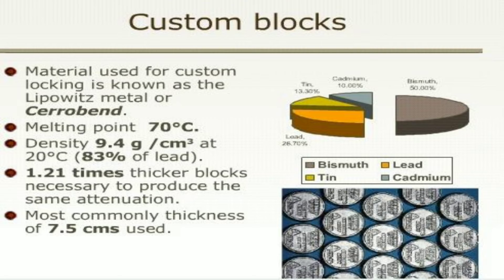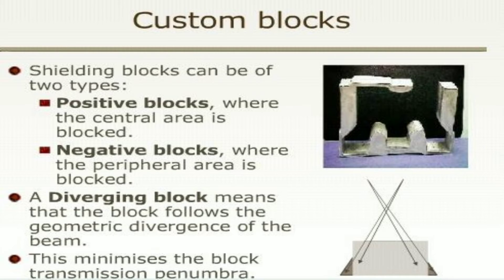Custom blocks are made up of Lipowitz/Cerrobend material which has a melting point of 70 degrees Celsius with a density of 9.4 grams per centimeter cube at 20 degrees Celsius, which is 83% of lead. 1.21 times thicker blocks are necessary to produce the same attenuation done by lead blocks, and the most commonly used thickness is 7.5 cm. Shielding blocks are of two types: positive blocks, where the central area is blocked, and negative blocks, where the peripheral area is blocked. In a diverging block, the block follows the geometric divergence of the beam, which minimizes the block transmission penumbra.